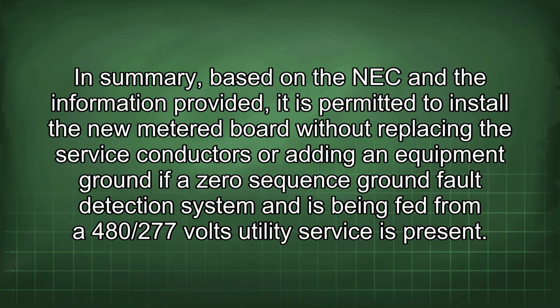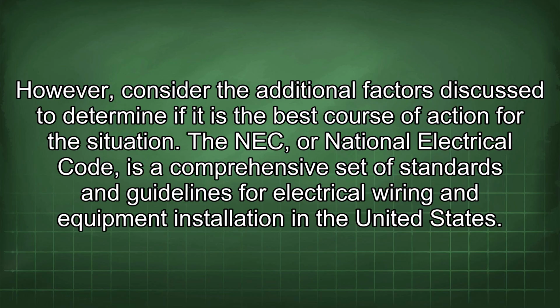In summary, based on the NEC and the information provided, it is permitted to install the new metered board without replacing the service conductors or adding an equipment ground if a zero-sequence ground fault detection system is present and the building is being fed from a 480/277 volts utility service. However, consider the additional factors discussed to determine if it is the best course of action for the situation.